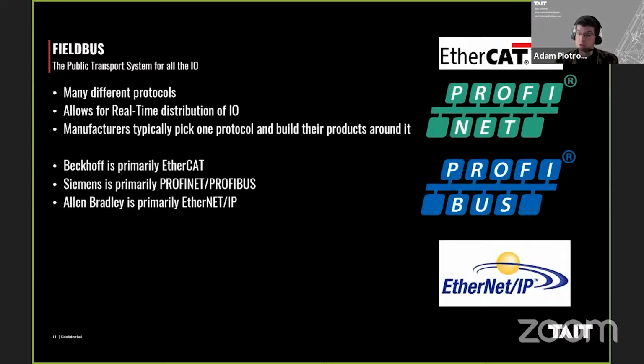This becomes a factor when we're doing control system design, because we need to make sure everything can talk. So if we've got a Siemens MCC and a Beckhoff controller, we need to find a way to get that EtherCAT communication over to Profinet type communication. That does exist, but it adds complexity to the system. We want to keep things as simple as possible so troubleshooting is straightforward, and any newcomers to the industry, installation, or project can be brought up to speed quickly. So this is what we use here at TAIT.